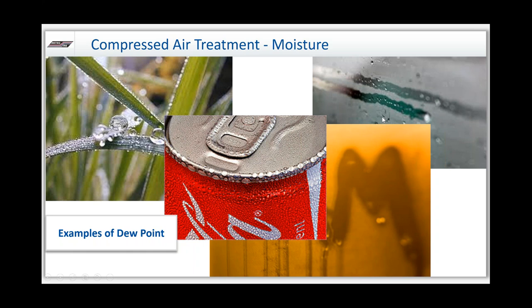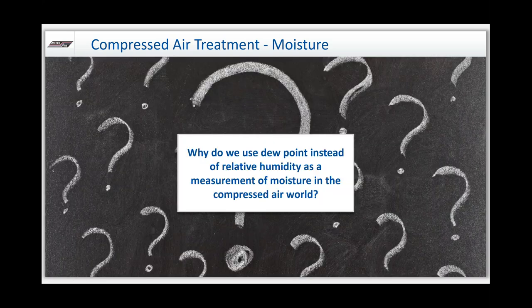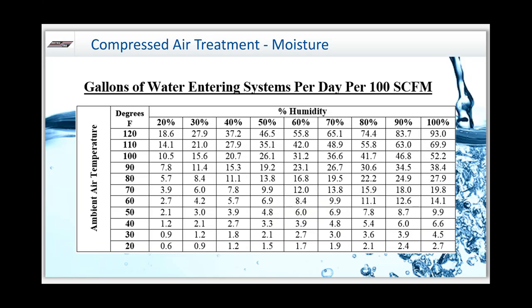Why do we use dew point instead of relative humidity as a measurement of moisture in the compressed air world? The simple answer is that it's an exact number. If I said I wanted a moisture content of 80 degrees and 50% relative humidity, as soon as the temperature changes, it's hard to know what that means. Dew point is a specific number — I want a 30-degree dew point in my compressed air system, meaning as long as the temperature stays above 30 degrees, I shouldn't see any moisture condensed in liquid form.